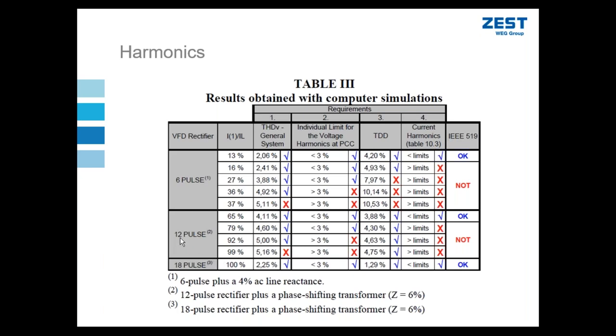If I replace those 12 pulse VSDs with, for example, 18 pulse VSDs, then even in the unlikely scenario that my 8 MVA utility transformer is 100% loaded with that VSD load, I still easily meet the requirement for IEEE 519. So I guess the takeaway point here is that if you can get away with the simplest case, which is a 12 pulse solution, go for it. If not, then start increasing the complexity as needed.